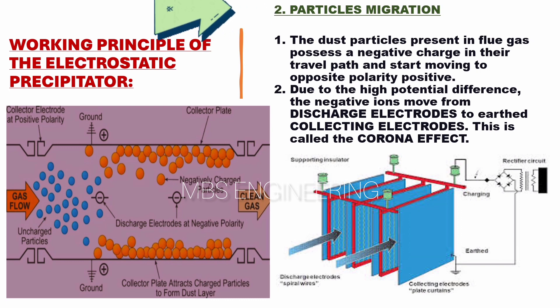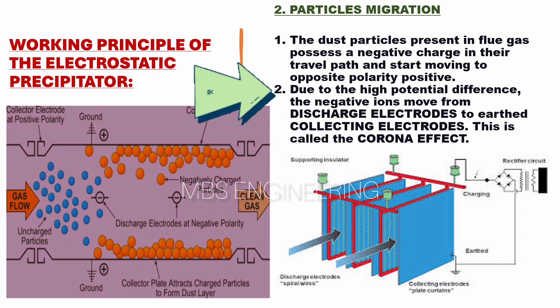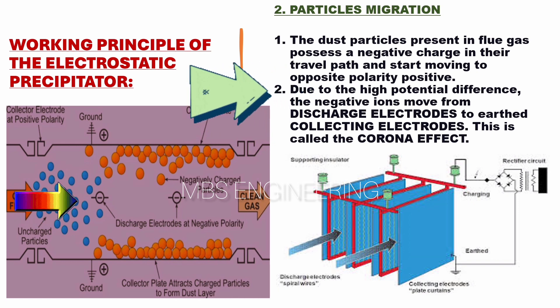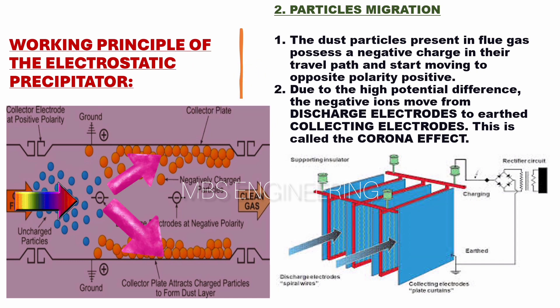The second step of the electrostatic precipitator's working principle is particle migration. The dust particles present in flue gas possess a negative charge in their travel path and start moving to the opposite polarity — positive. Due to the high potential difference, the negative ions move from discharge electrodes to earthed collecting electrodes. This is called the corona effect.